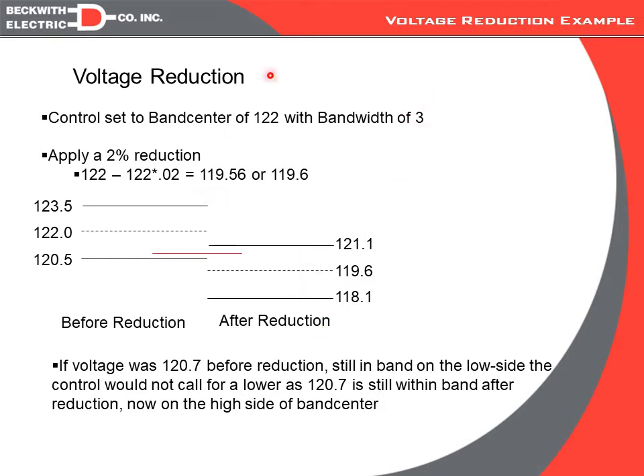So basically what we've done is we've changed the band center from 122 to 119.6, and that's all we've done. And we can see that if the voltage was in this area right in here prior to issuing the command, we will not even do a lower after going into reduction, because the voltage would still be in band on its new band. So we just went from being on the low side of the existing band, or the original band, to now being on the high side of the new band.